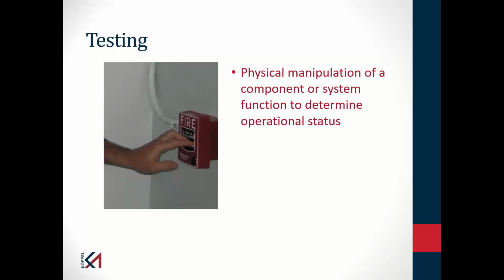Now, testing is something that causes us to physically activate something. We're going to pull this pull station, and this pull station is going to actuate the fire alarm system. In a sprinkler system, we're going to flow water to see that the alarm system actuates. So we're doing a function to make sure that the system is in proper operating condition.